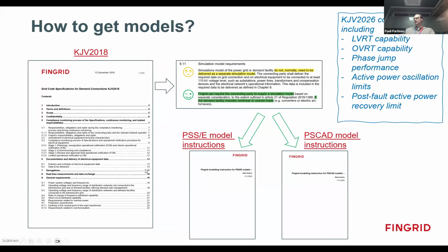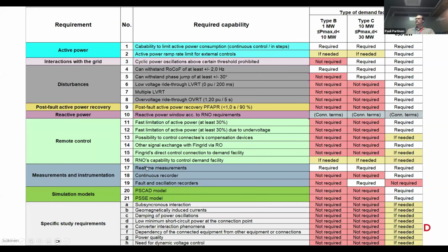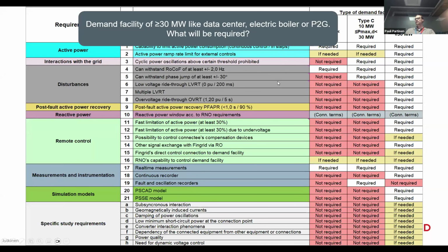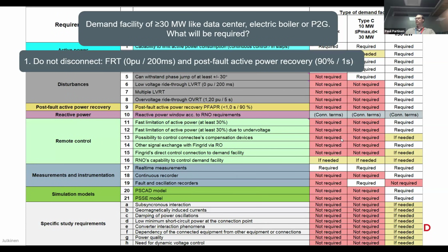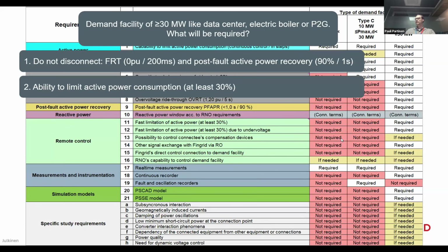And since we did that, I also wanted to take this one slide from last Friday. I won't go through this, but these are the requirements that we are now implying for our connectees. It is based on what kind of nominal active power you have in your demand connection. For example, for a demand facility over 30 megawatts, like a data center or electric boiler, what will be required is: do not disconnect in fault ride-through, and the post-fault active power recovery must be below 1 second. Ability to limit active power consumption from a signal at least 30%.